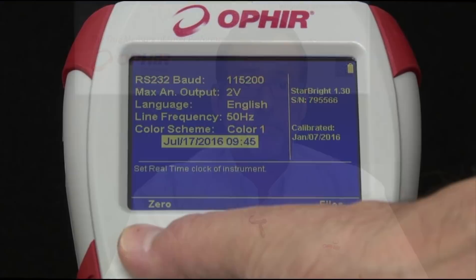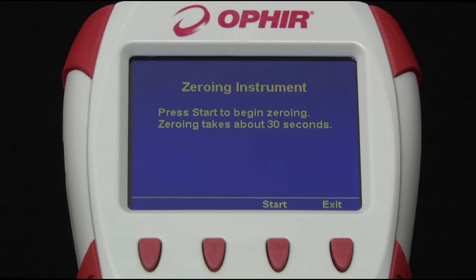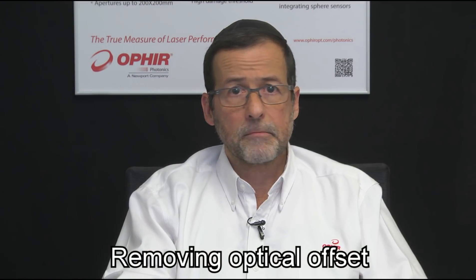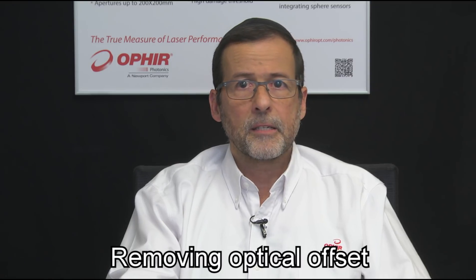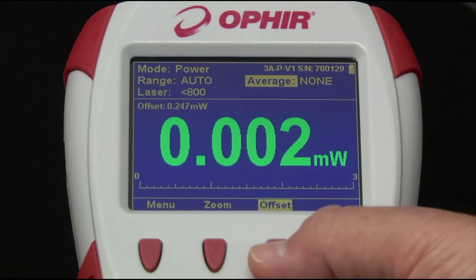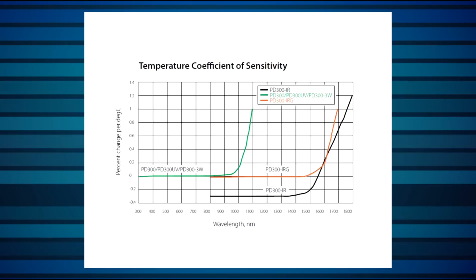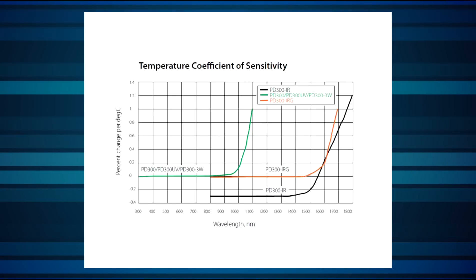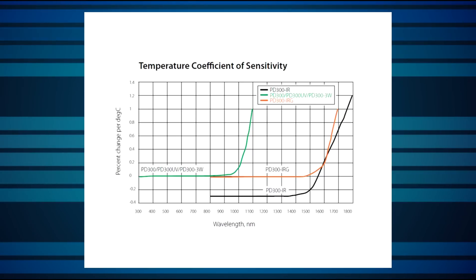For dealing with offset, zeroing the instrument removes electrical offset that builds up over time. We recommend doing this periodically, say every month or so. Optical offset — unwanted background light or heat — can be removed using the meter's offset function. Turn off or block the beam without affecting anything else, then check if the reading is in fact zero. If there's any offset, use the offset function to automatically subtract this value from subsequent measurements. For photodiode sensors, check that your measurement conditions won't cause temperature effects. Graphs of the relevant temperature sensitivity coefficients are found in our catalog and on our website.